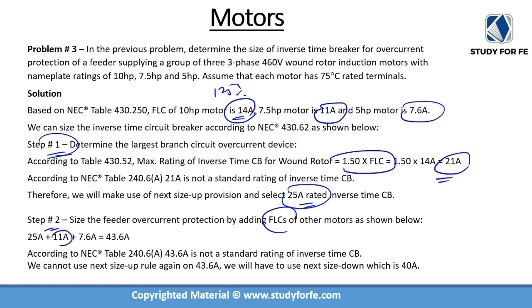So 11 amps plus 7.6 amps plus 25 amps gives us 43.6 amps. Another common mistake is sizing up because 43.6 amps is not a standard rating — but that is not allowed in step 2. You may go to the next higher rating in step 1, but in step 2 you can only size down. Since 43.6 amps is not a standard rating, the next size down is 40 amps, which is the correct answer.